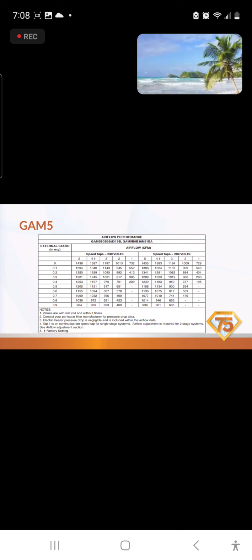Here would be an example of the air handler, the GAM5, also a constant torque motor, but we don't have 9, we only have 5 speed taps. It is done a little bit differently. We're not going through the 7-segment display. You literally have to move a wire from post to post like you did on the old PSC motors. But here, this is the GAM5 with a 3-ton. If you look here, speed tap 1, 2, 3, 4, and 5 is going to change depending on your voltage. So it is important, not only do we know our static pressure and our speed tap, but on the air handlers, you also have to know your voltage, because you could have a 208 or a 230, 240, and that's going to change your CFM.